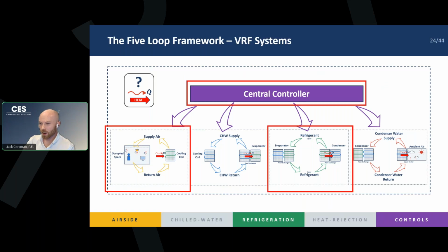So how does VRF look? We're just using controls, our supply air loop, and our refrigeration loops. We don't have any chilled water, as Matt said earlier, right? Desert application, you don't have anything, but it can be applied for a wide variety of applications that also don't want to use chilled water or don't want to use condenser water. So in this VRF application, we're taking advantage of using 3 system loops.